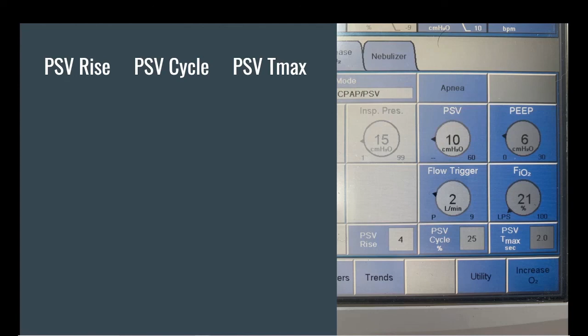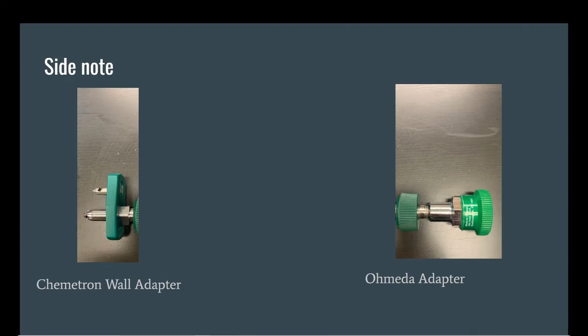As a side note, we have the Chemetron wall adapter. We take our tubing, screw it into the Chemetron wall adapter, and plug it into the wall of the hospital. Hospital outlets have either the Chemetron or the Ohmeda adapter. We have both. What we have done, coming to a CC gray bag near you soon, is connect these two. That way we can click into the wall and quick click into the Ohmeda connector from the tank, and then quick disconnect and quick connect into our tank when it's time to move the patient from the wall oxygen over to our portable tank. So these will be coming to the CC bags soon.